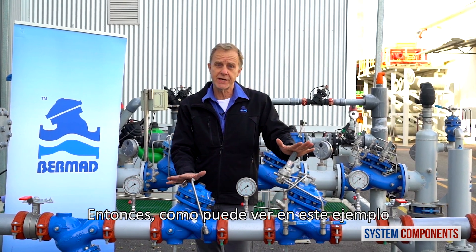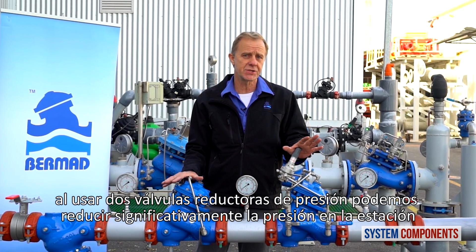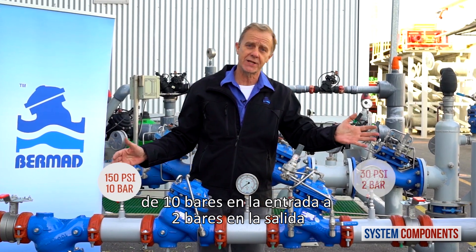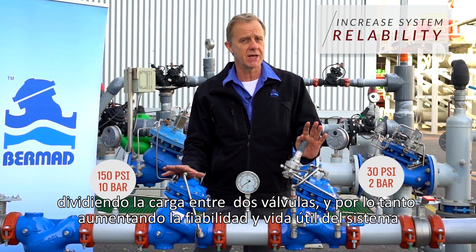So as you can see in this example, by using two pressure reducing valves, we are able to significantly reduce the pressure across the station from 10 bar at the inlet to 2 bar at the outlet, dividing the load with two valves and thereby increasing reliability and service life.